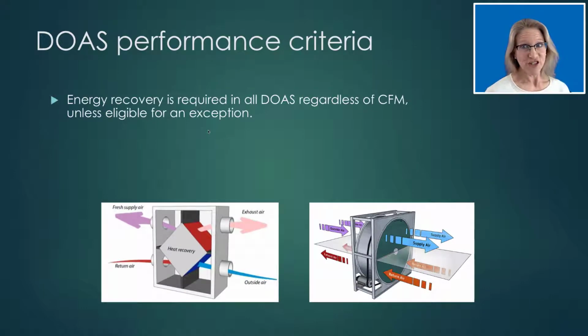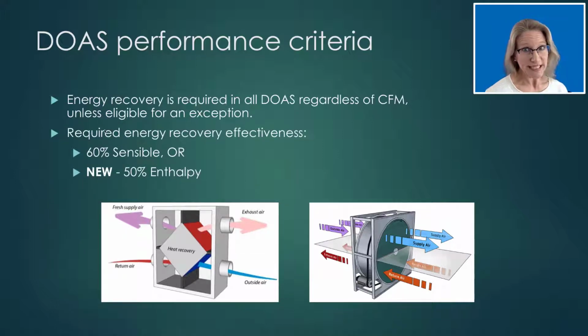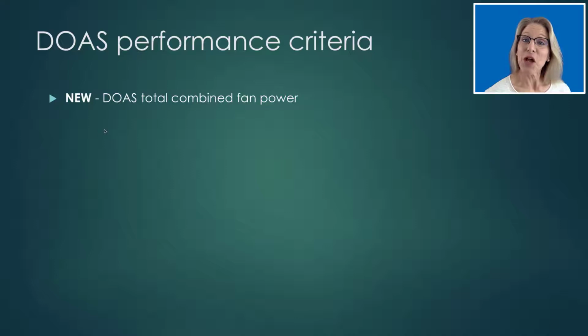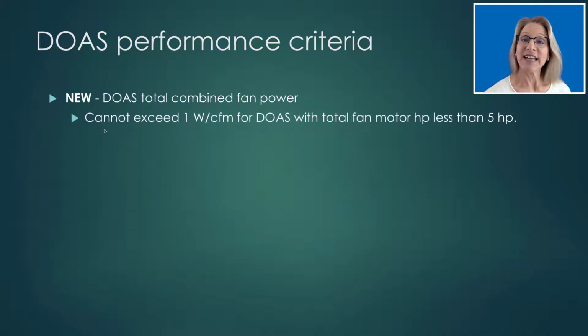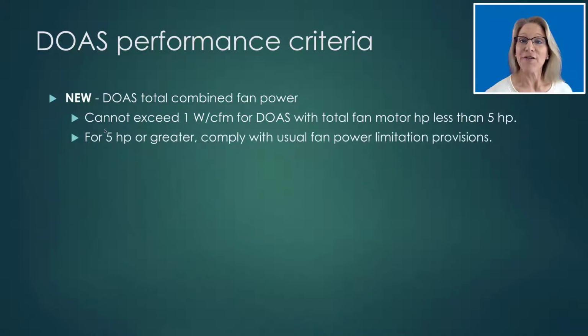So there are two changes to the performance requirements for DOAS. A system may comply via sensible only energy recovery effectiveness, or it may now comply via enthalpy, which accounts for both sensible and latent recovered energy. Also, for fan efficiency, the code now defines a maximum of 1 watt per CFM for a DOAS with total fan motor horsepower less than 5 horsepower. For a DOAS with fan motor horsepower equal to or greater than 5 horsepower, the system is required to comply with the usual fan power limitation requirements.